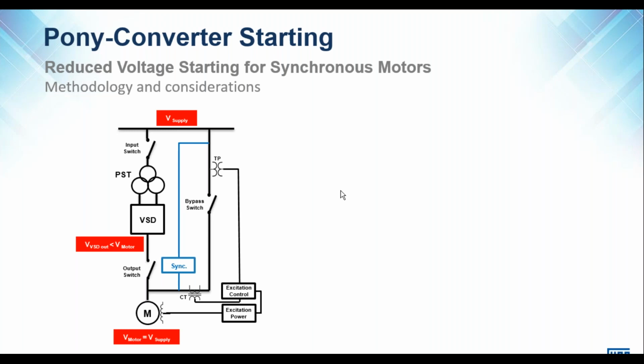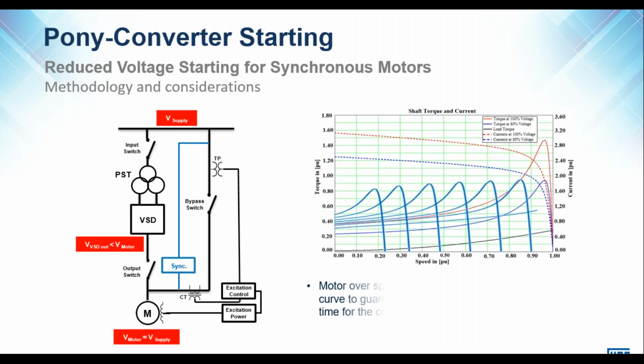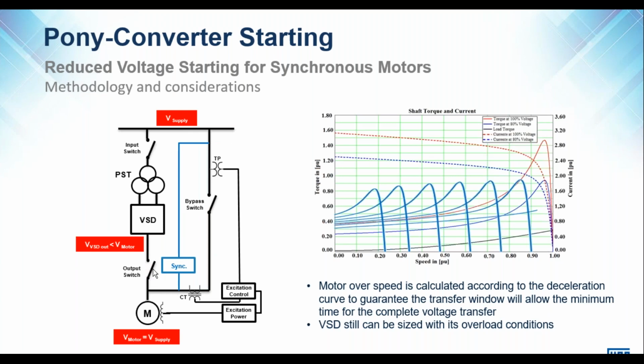We can do exactly the same on synchronous motors. I'm not going to go into too much detail. Essentially, it is the same with one small difference, and that is during synchronization, we have separate excitation control on the field winding of the synchronous machine. And so we can actually use this to our advantage. Previously we looked at two scenarios where we have a reduced VSD size to start certain motors, and the condition where we have both a reduced VSD size and reduced voltage to start certain applications. In the case of a synchronous motor, we can make use of a reduced size VSD with reduced voltage and use the excitation control to actually benefit us and increase the voltage before we do the bypass.